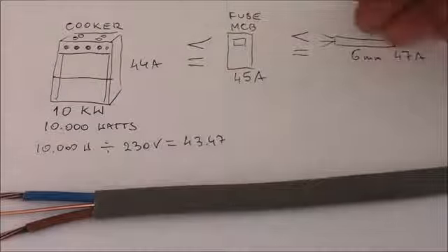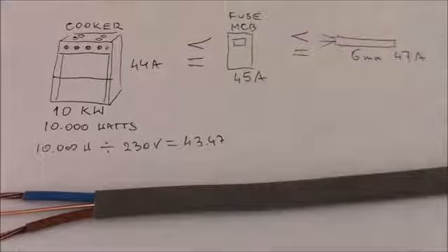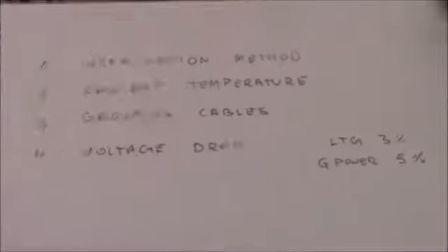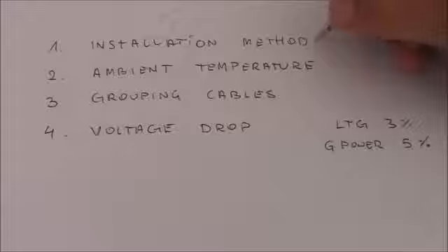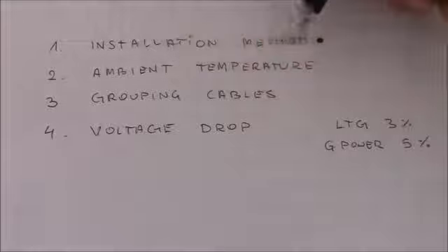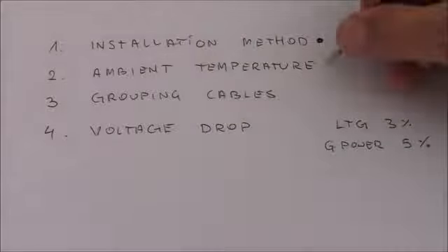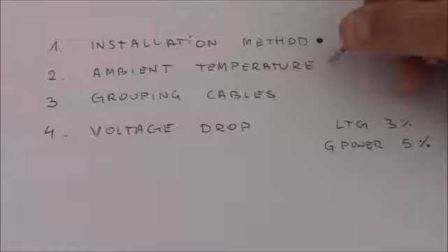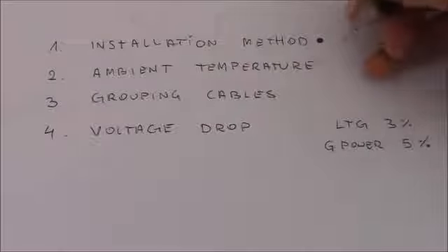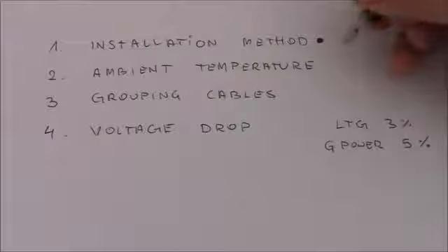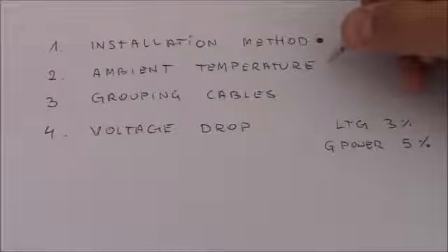So that's the very basic calculation, but there are some other factors that you need to consider when choosing the right cable for the circuit. The first one is the installation method. That's what we were talking about, how you install the cable. So we've done this. Now the ambient temperature. That's the surrounding temperature of the cable. Don't install the cable near a boiler or near the radiator pipes, as they can easily overheat. They cannot dissipate the heat when they're warming up.